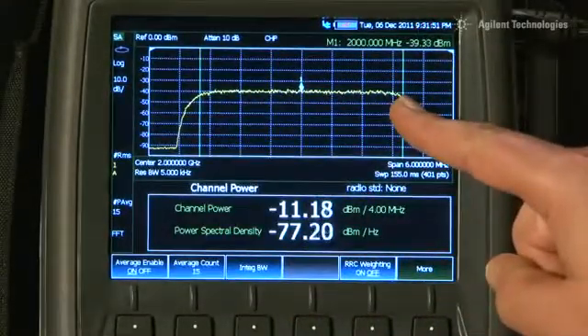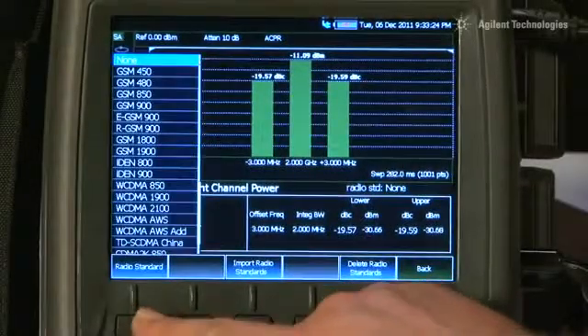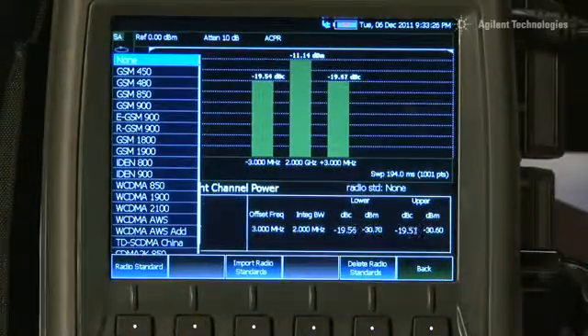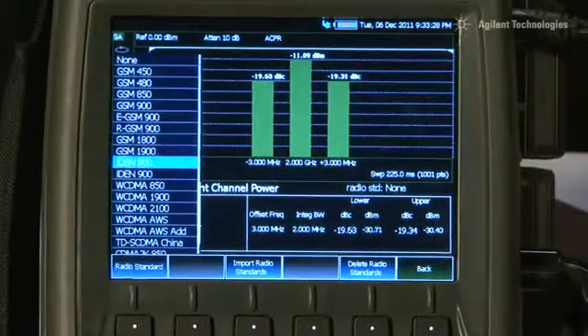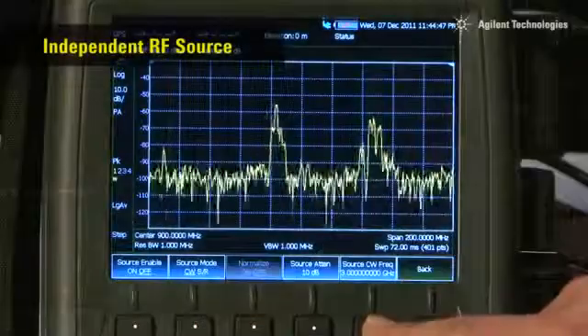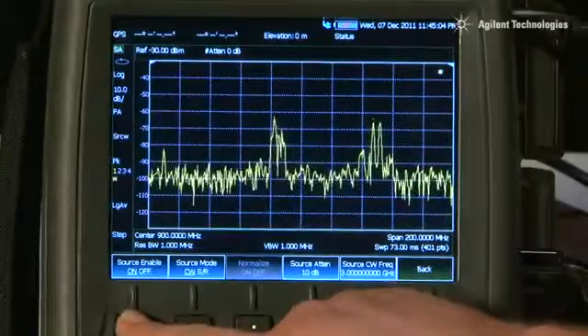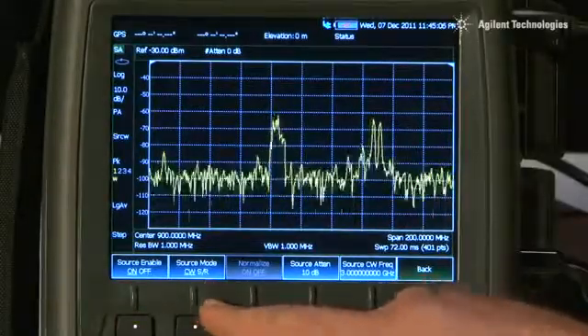And all these are available for predefined standards such as LTE, WiMAX, GSM, CDMA, WCDMA, CDMA2000, etc. And while using the FieldFox as a spectrum analyzer, you can use the internal RF source as a stand-alone fixed frequency signal generator. It can be set to any frequency and you can use it to check interference, use it as a test signal or even as a portable RF beacon.